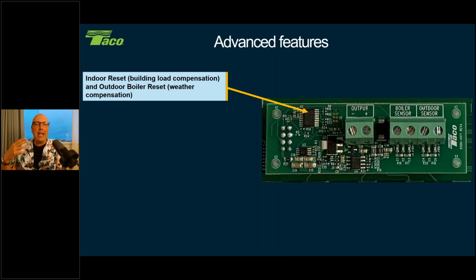What do I mean by indoor reset or load compensation? What this is going to do, it's going to use only the boiler supply temperature sensor, and it's going to modulate that water temperature based upon run times of the zones. If your zone running times are recorded and they start to be really short, that means the water temperature is really high. So we want to start lowering it so we get longer run times of my zones, and that starts to drop that water temperature. So it starts to do the programming all on its own. All right, and looking at that runtime of zones and water temperature being sent out there.